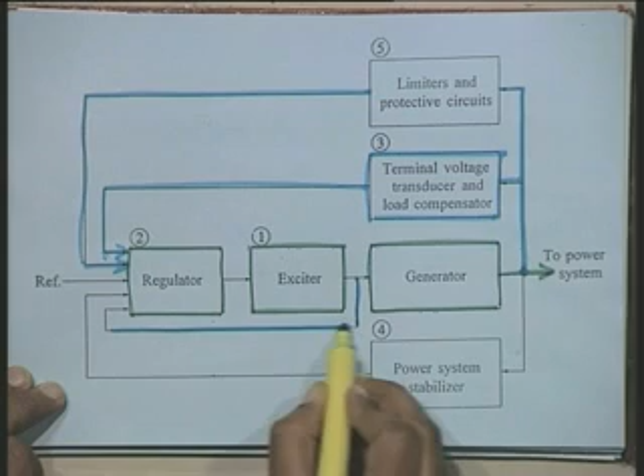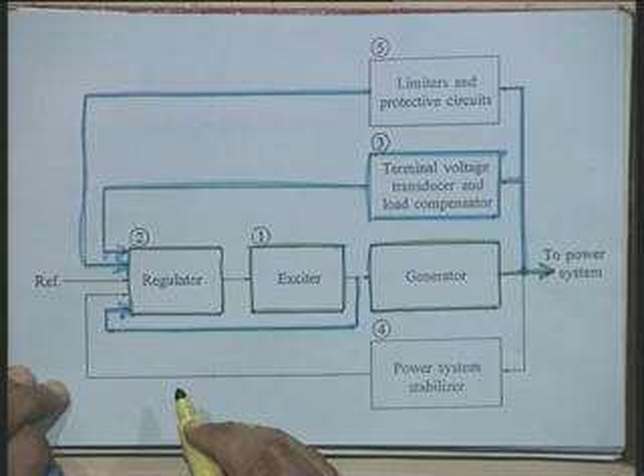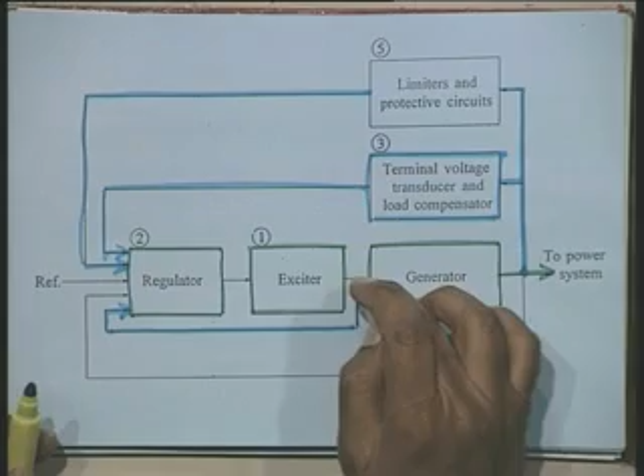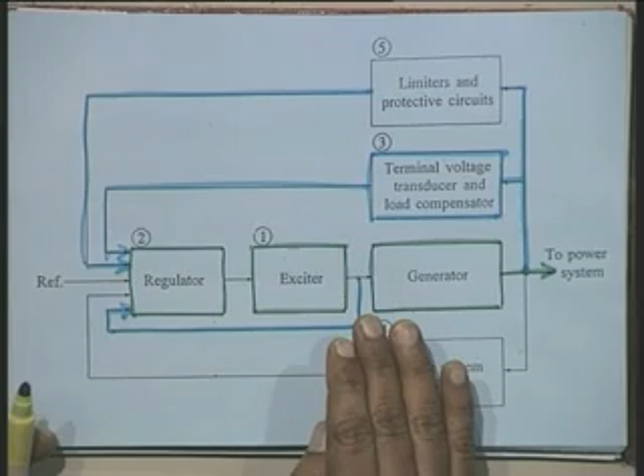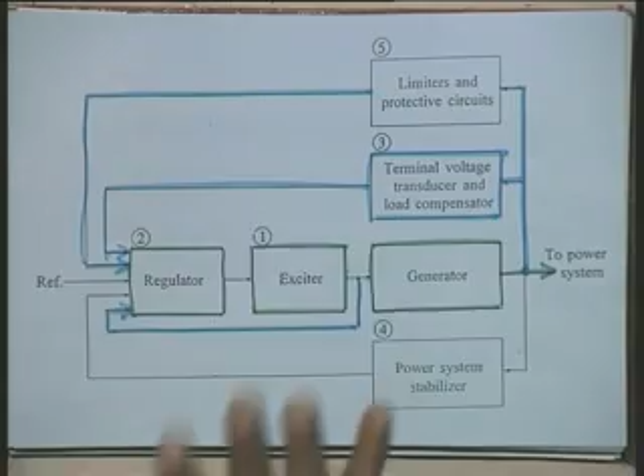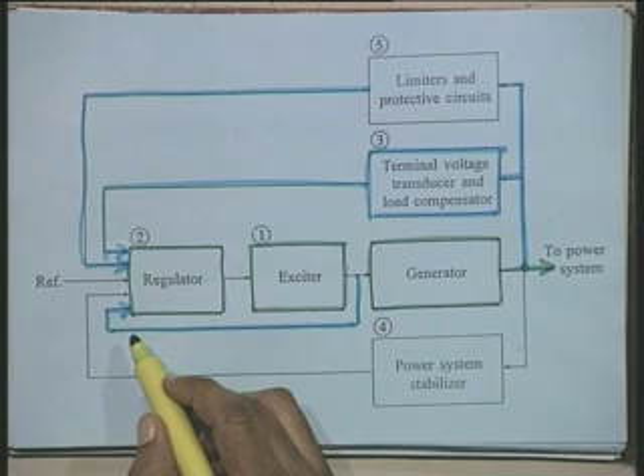Then you have one feedback loop around the exciter. This loop we generally call the excitation system stabilizer. That is, here you sense the output of the exciter, okay, and in case you do not have this feedback loop, then the exciter itself may become unstable, because once you have a closed loop control system, stability is a very important requirement. Therefore, you will find that there is one feedback loop, that loop is called excitation system stabilization, okay, and that again operates through the regulator.